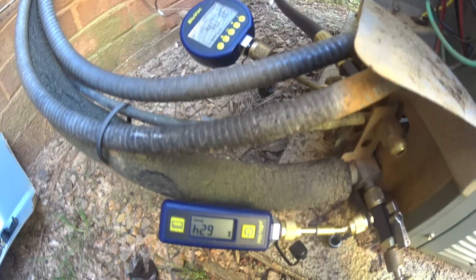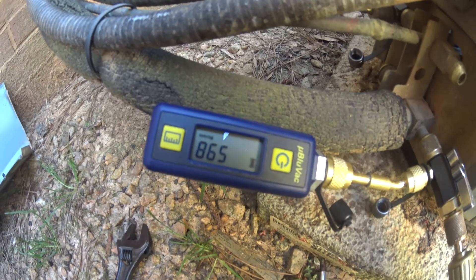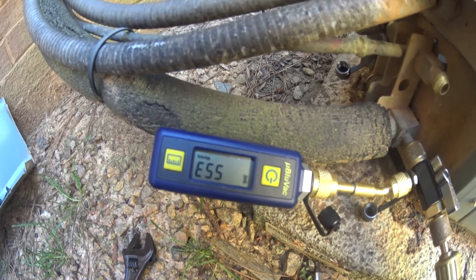Let them both read what the vacuum's pulling from the tip and let it run for a little while. As you can see, that BluVac — the original BluVac — is under 500 already, and this one's not far behind. We'll let them both run for a bit and we'll be right back.